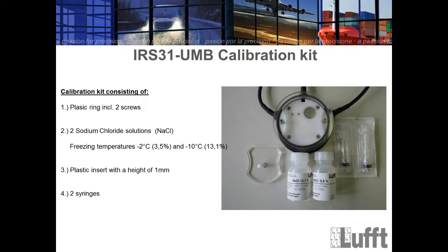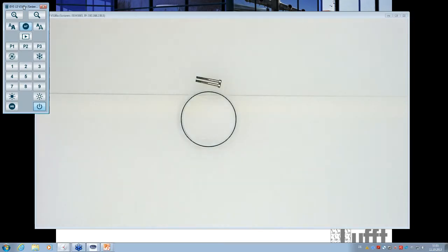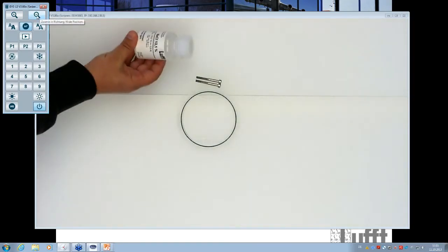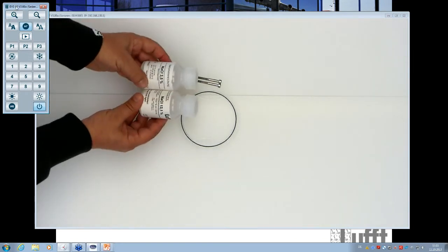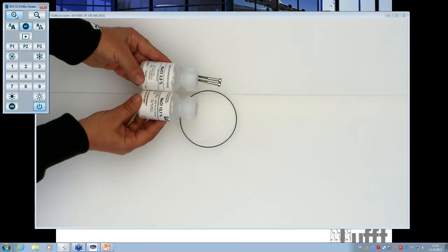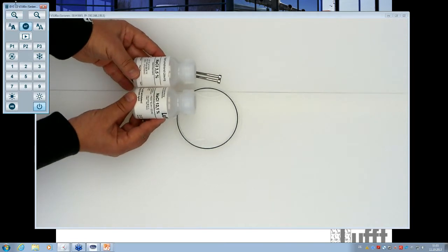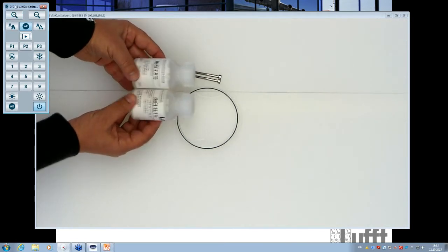Then we have 2 sodium chloride solutions, natrium chloride, for freezing temperatures: minus 2 degrees, which means 3.5% of sodium chloride, and minus 10 degrees Celsius, which is 13.1% of sodium chloride. Again, I will show you that live here. So we have one bottle and the second bottle, 3.5% natrium chloride and 13.1% natrium chloride, which are part of the calibration kit.